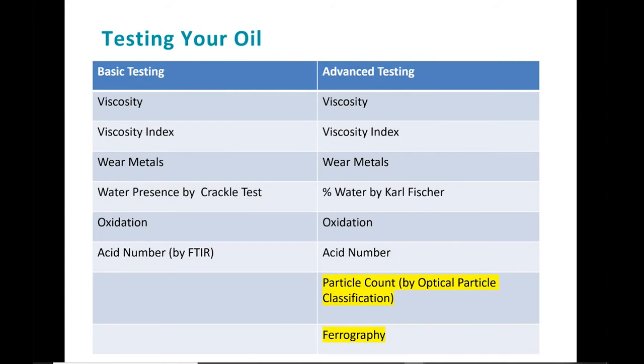Here's a breakdown of basic and comprehensive testing. The basic testing covers wear metals, viscosity, the presence of water, oxidation, and acid number. While this gives a great high-level view of what's going on in your reducer, the more advanced testing can help you dig deeper into results by doing things like particle counts and ferrography.